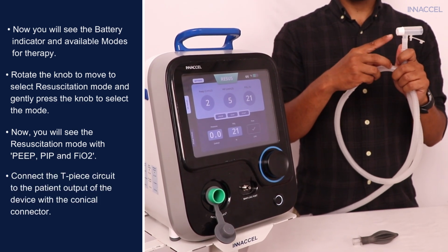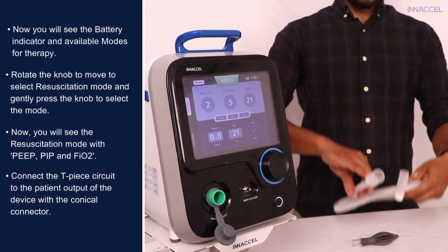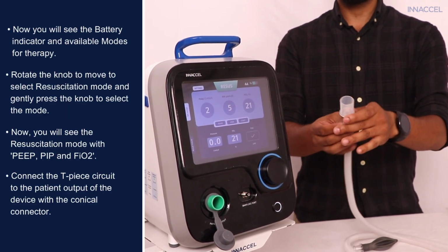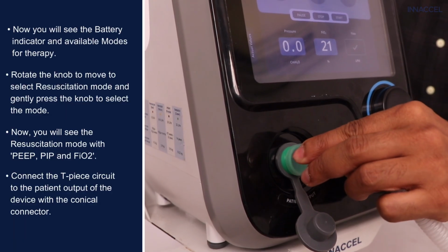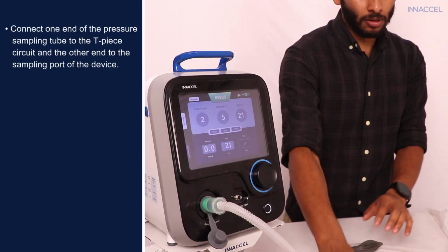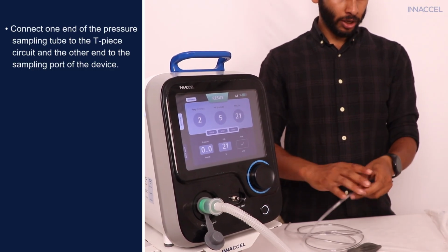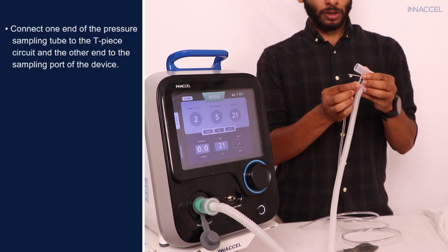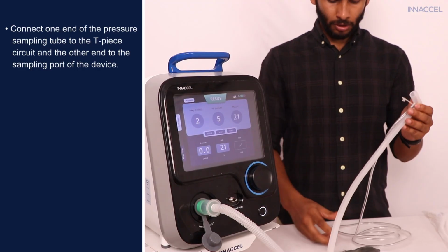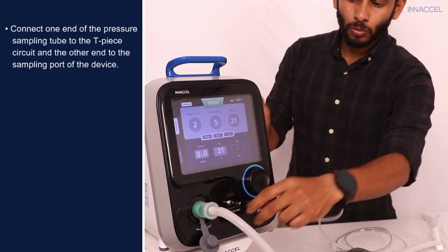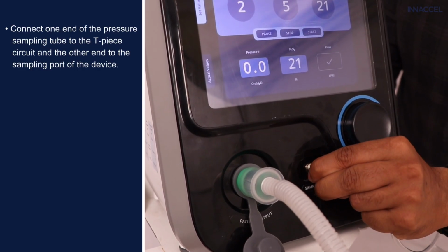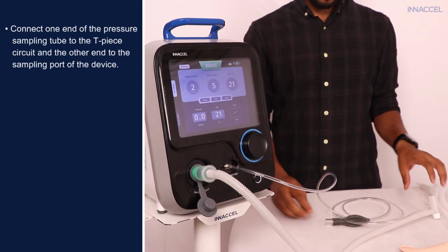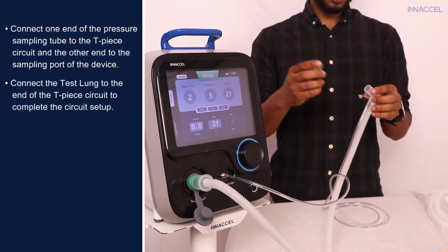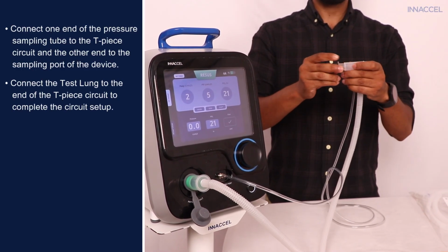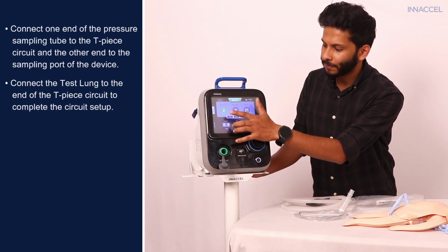Connect the T-piece circuit to the patient output of the device with the conical connector. Connect one end of the pressure sampling tube to the T-piece circuit and the other end to the sampling port of the device. Connect the test lung to the end of the T-piece circuit to complete the circuit.